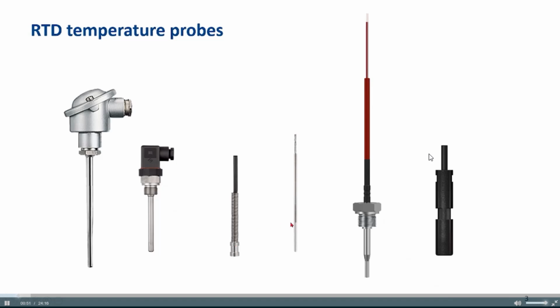Here we have the sheath thermometer, which we have in this world of RTD temperature probes as well. A cable probe, and here we have a plastic probe, which you can use in an area where you have extreme high voltage, in a motor or something like this. So those are RTD temperature probes, and I want to give you a little better idea of how to work with them.